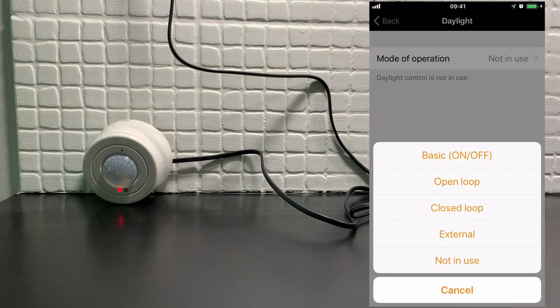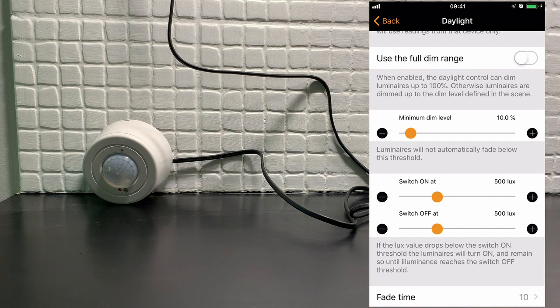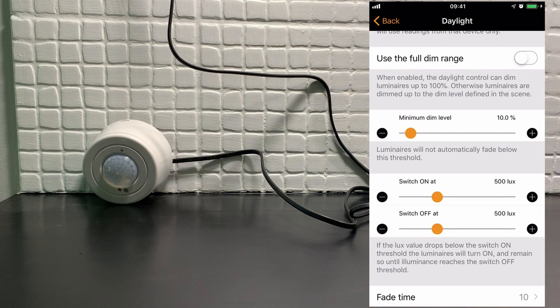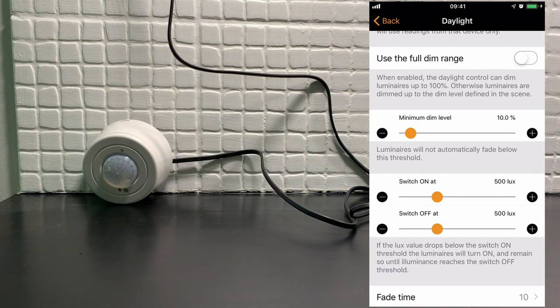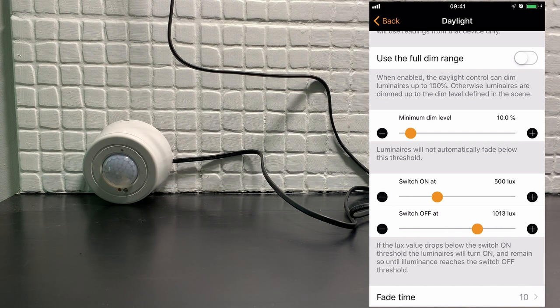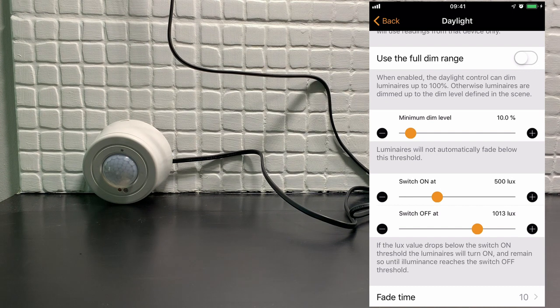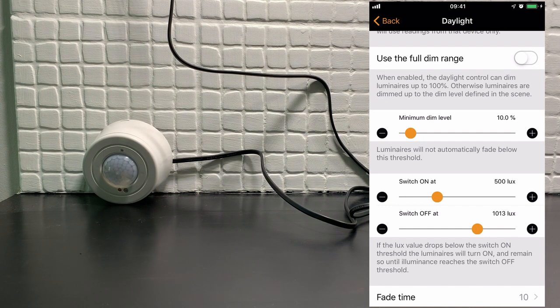You're then presented with a number of modes. Basic on-off allows you to define at which point the scene turns on the luminaire and turns it off. Right now, for example, it would turn on the luminaire when it reads 500 lux and turn it off when it reads 1013 lux.